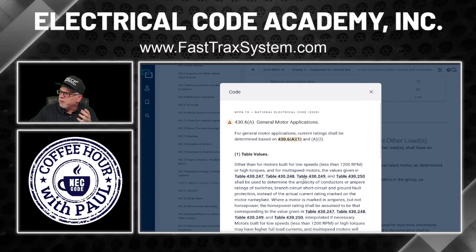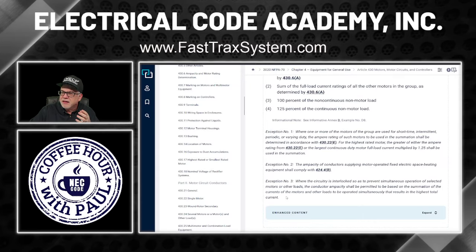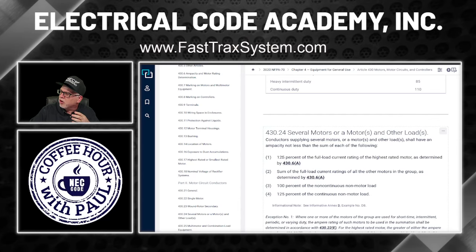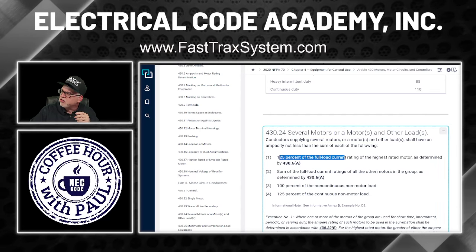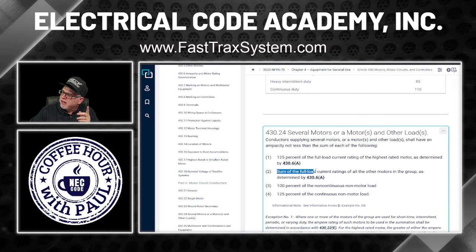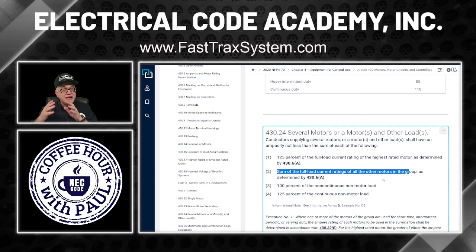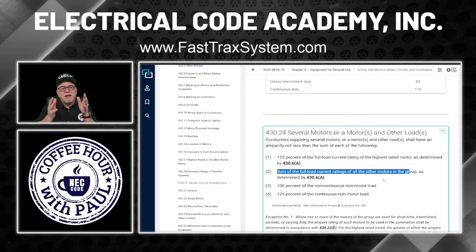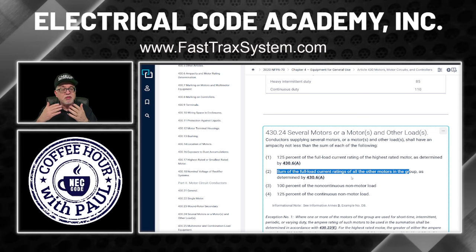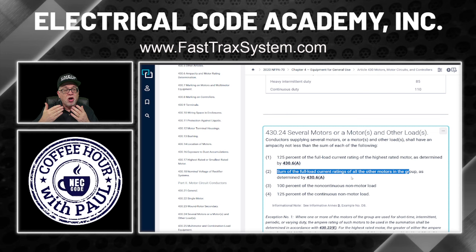And so, for example, if I were to click on that table, it looks like it didn't go there, so we're going to have to go there. Okay, so 125% of the FLC of the highest rated motor, and then it says the sum of the FLC rating of all the other motors in the group. That means they're connected to the same phases as the first motor, so they're in the same group, right? Okay, so 125%. Now, both of these are the same, so you just pick one of them and do it at 125% and then 100% of the other one.